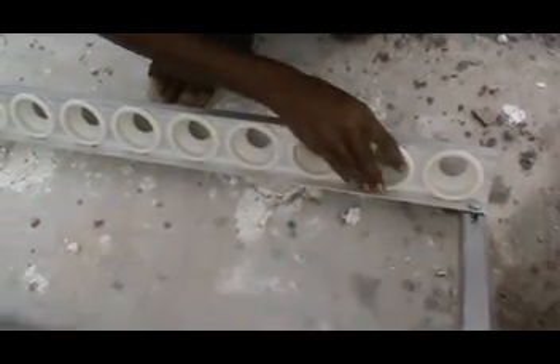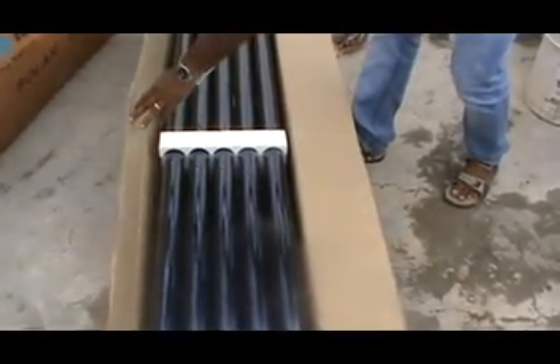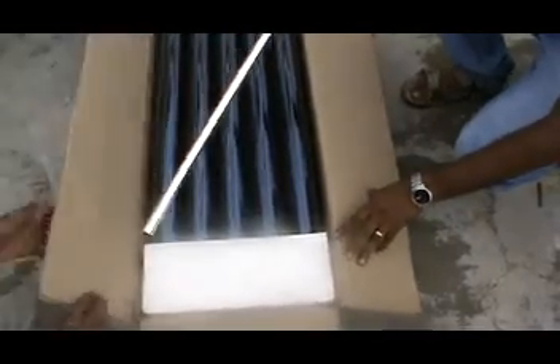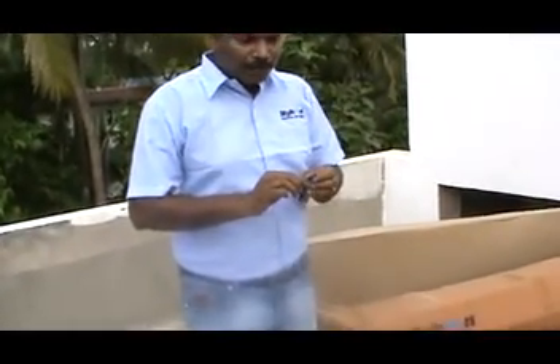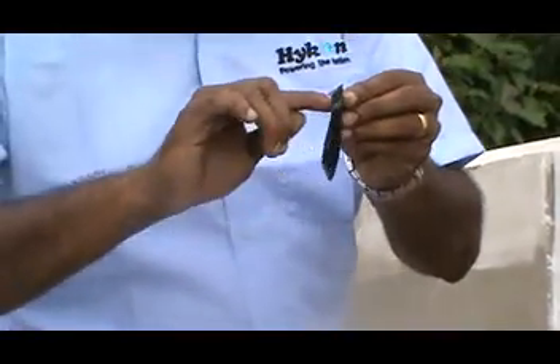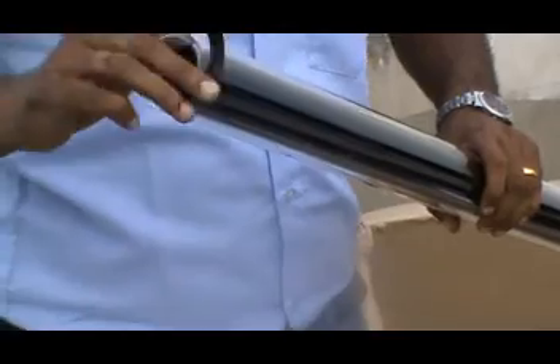The last step is fixing the glass tubes. We open the glass tube box — this is what the evacuated glass tube looks like, manually packed with thermocol fixed at both ends. Before inserting the glass tube, we fix the dust seal on the tubes. We lubricate the dust seal and also lubricate the tube itself, then the dust seal is inserted onto the tube.